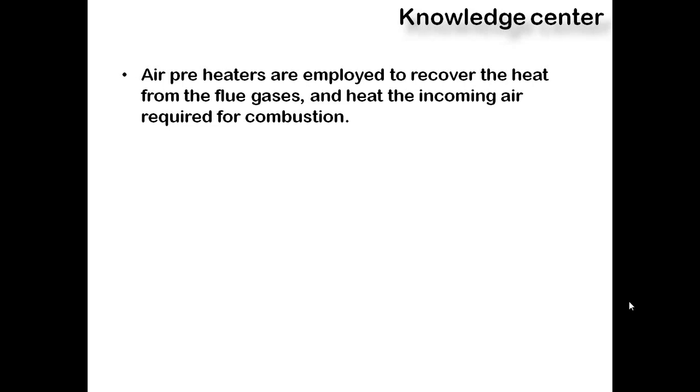The heat which was available with the flue gas will be shifted to the incoming air, and that hot air will be given to the boiler. So for combustion, instead of getting normal air with a low temperature, if you get air with a high temperature, then the requirement of fuel to heat up the air will be less.